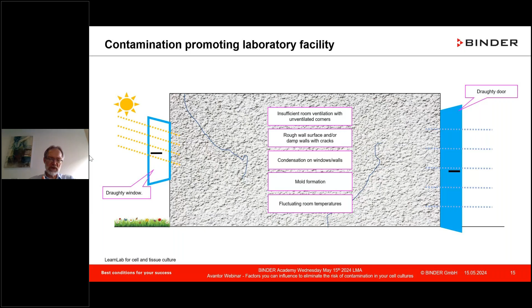Now you can refurbish this, and this was nicely done by Professor Know-It-All right here. And you can see the walls are nice and clean, very smooth, no cracks, molds are gone. And we have different issues, like to point out ventilation of the entire room, an HVAC system. And the ideal temperature for a cell and tissue lab is somewhere between 18 and 30 degrees. We had a representative of a cell and tissue culture company over here from Thailand, and they even said some days they even achieve 30 degrees C. But the best optimal temperature right here for a CO2 incubator is around about 22 degrees and a maximum 70% RH, relative humidity.